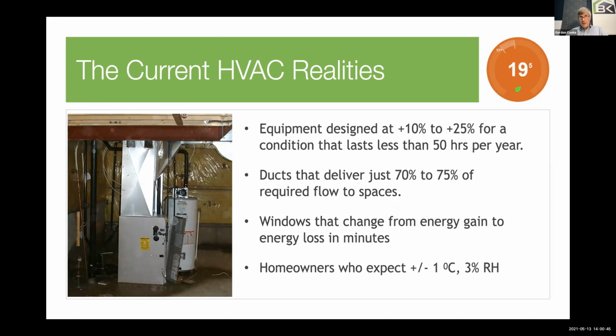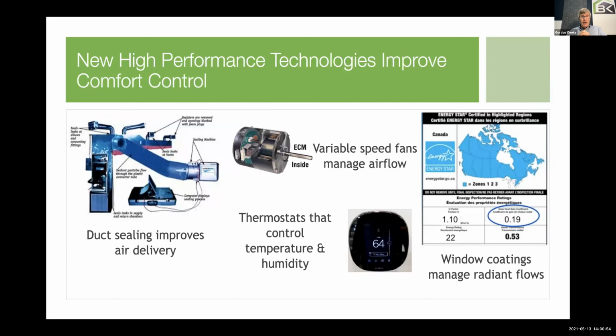They expect within 1 degree Celsius, 2 degrees Fahrenheit, and plus or minus 3% RH. We have those issues. But I am going to say there are some great technologies. You will recognize, hopefully on the left, duct sealing technologies that can get you down to 2% leakage. The good news, right there in the center, is that all air handlers now have ECM variable speed fan motors, or the equivalent, which gives you much better ability to manage airflow. This is a huge win for our industry. Yes, they're more efficient, but they also have better airflow flexibility. They're not a panacea, but they give you better control.